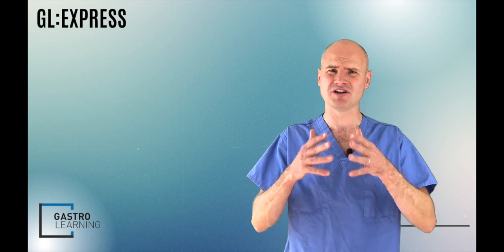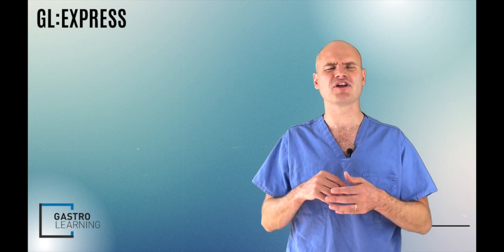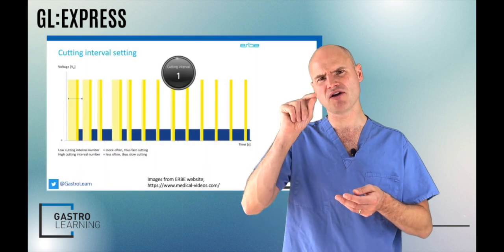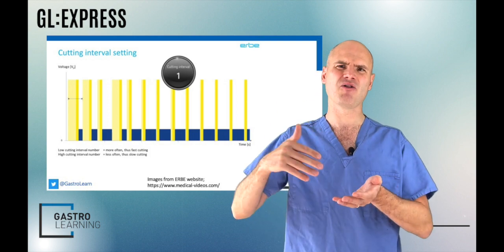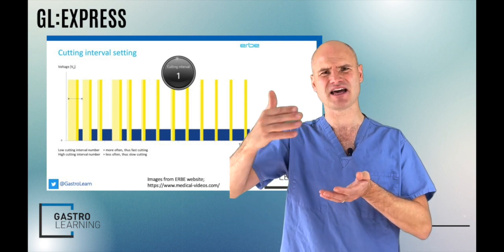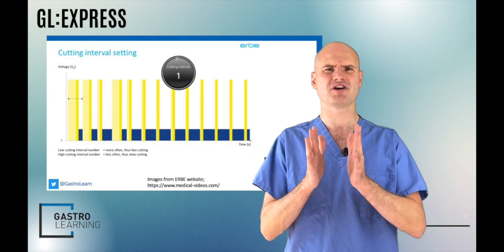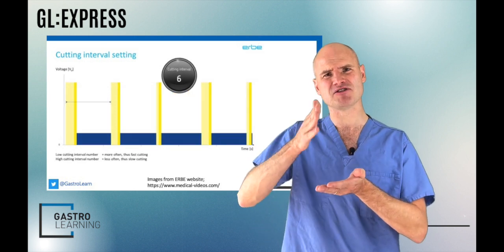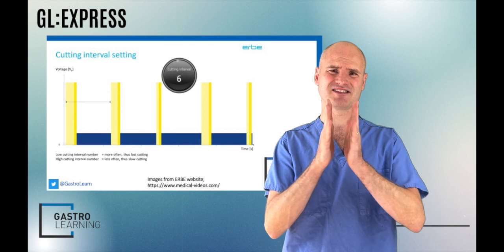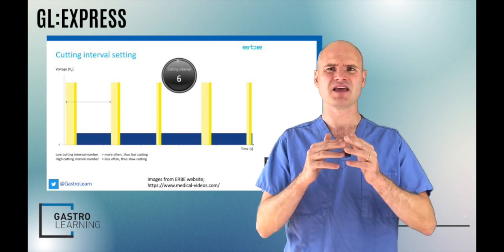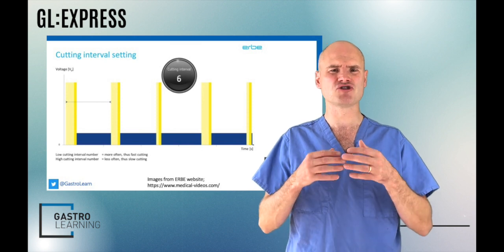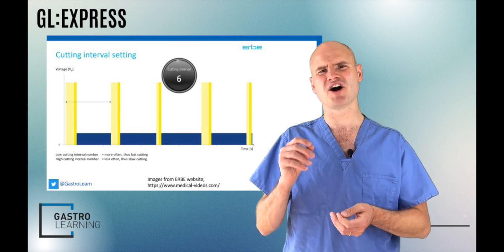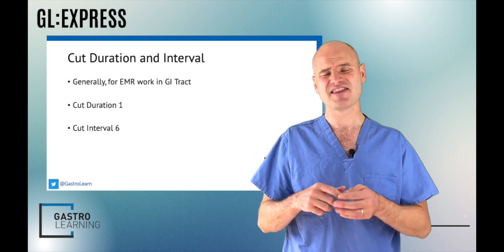Moving on to the cutting interval, this is the time between those high voltage cutting times where the tissues can cool down and we allow that effect, that coagulation phase, to happen. The shorter the cutting interval, the less time there is between the cuts and therefore the less time there is for that coagulation phase to happen. Generally speaking, the machine selects this for us and the majority of the work we do, we want the cutting interval to be set at six. That's pretty much for all EMR work.